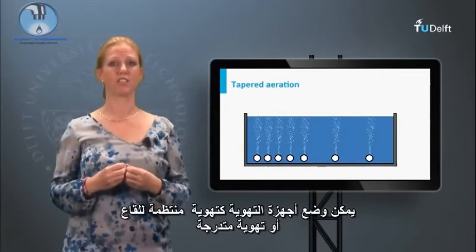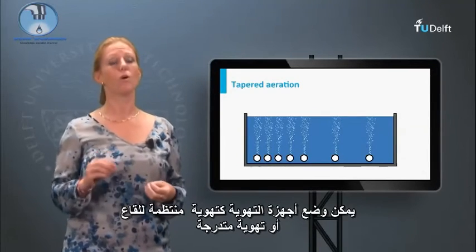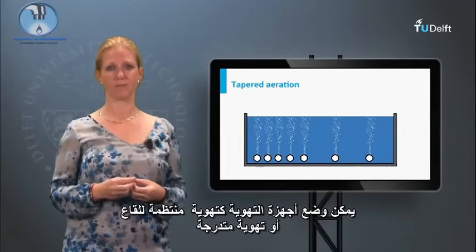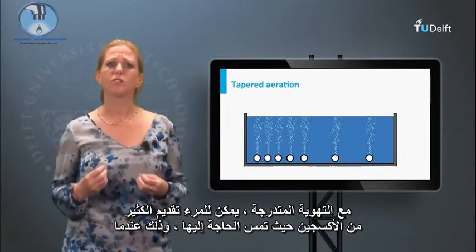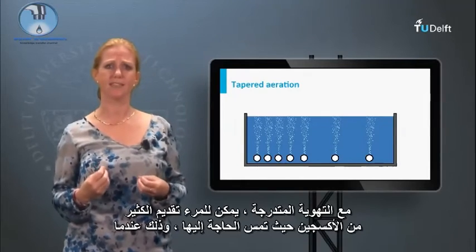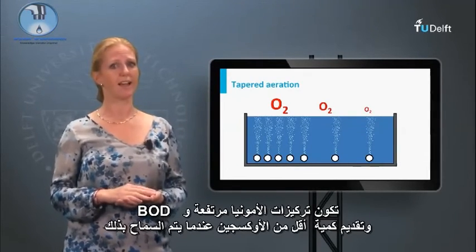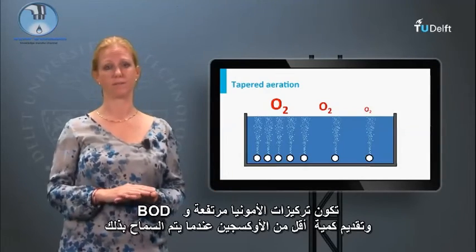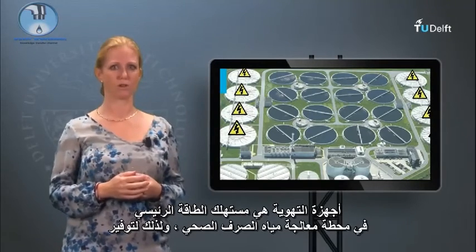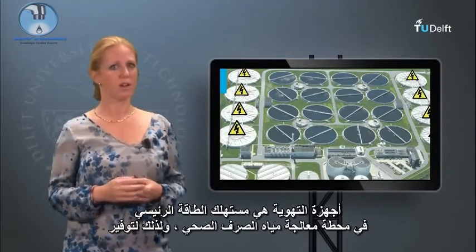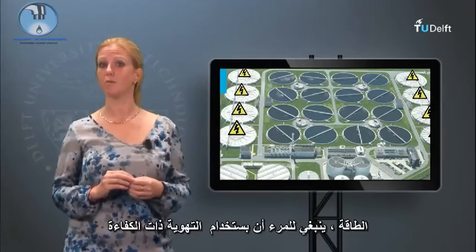Aerators can be positioned as uniform bottom aeration or as tapered aeration. With tapered aeration, one introduces lots of oxygen when it is needed — so when BOD and ammonium concentrations are high — and less oxygen when it is allowed. Aerators are the main energy consumers of the sewage treatment plant, so to save on energy one should use efficient aeration.